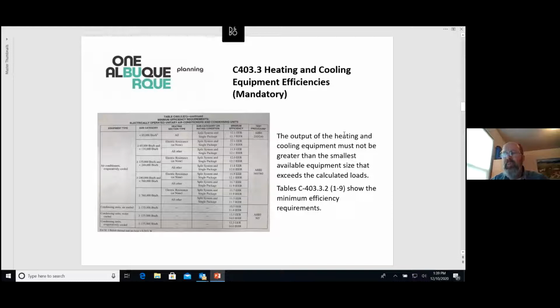The output of the heating and cooling equipment has to be not greater than the smallest available equipment that satisfies the need. So say the requirements are for 2 3/4 tons of cooling. Well, you would have to put a 3-ton unit in, not a 3.5 or a 4. They want the smallest piece of equipment that does the job. Not, I've got a 5-ton on the shelf, I'm going to put that in. So that will be something we will be looking at to ensure, probably in plan review as well as on the job during inspections.